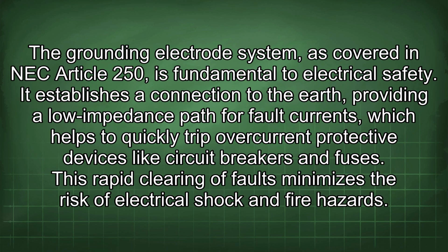The grounding electrode system, as covered in NEC Article 250, is fundamental to electrical safety. It establishes a connection to the earth, providing a low impedance path for fault currents, which helps to quickly trip overcurrent protective devices like circuit breakers and fuses. This rapid clearing of faults minimizes the risk of electrical shock and fire hazards.